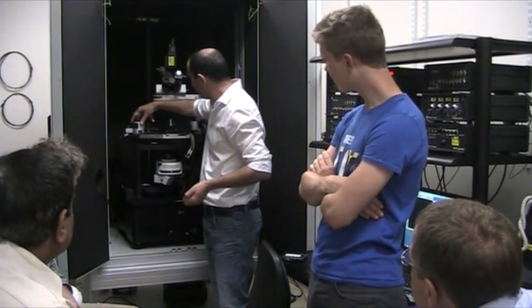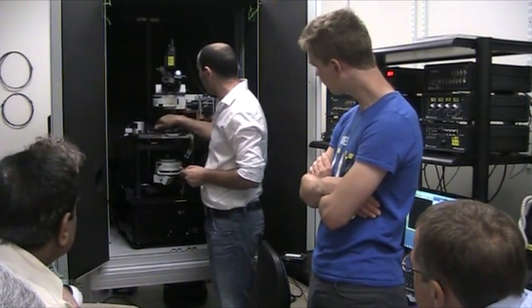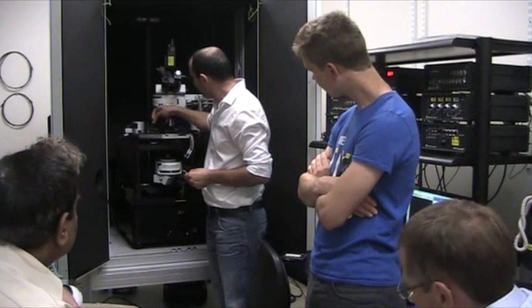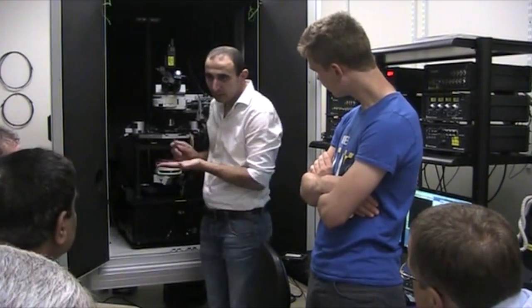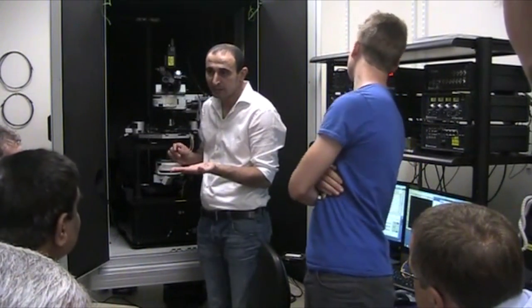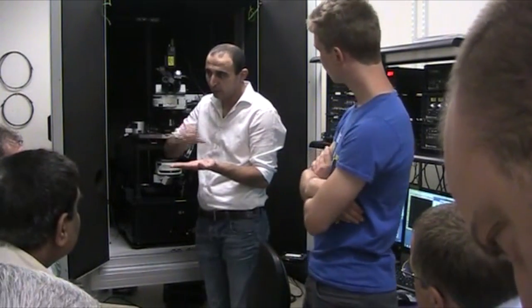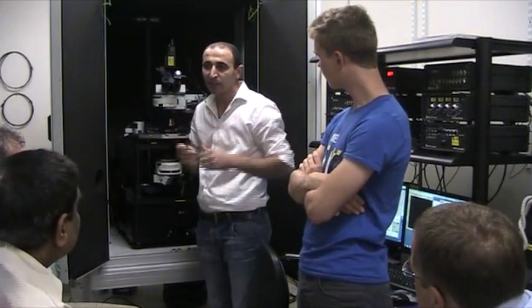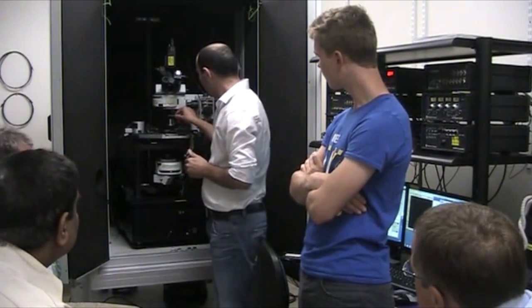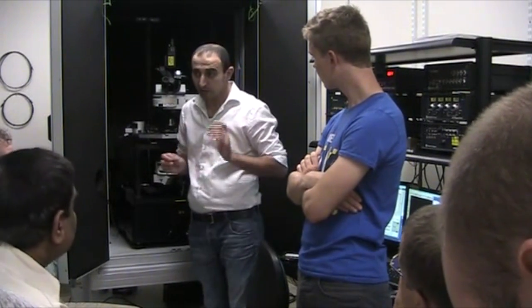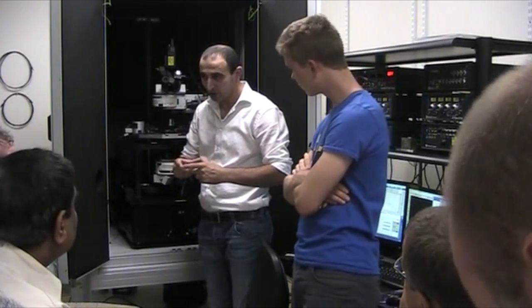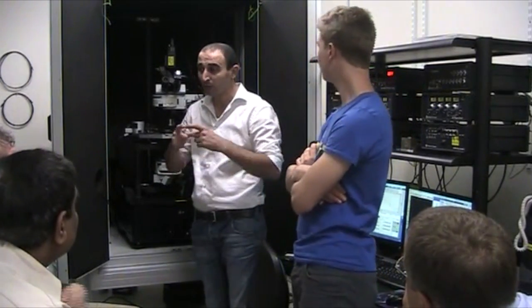this is the part. This is the AFM head together with the sample scanning stage. So in this system we have two AFM heads, okay? The right tower and the left tower. Every one of these towers also includes a tip scanning stage. So in general you have one sample stage, one to move the sample in X, Y, and Z, and an additional piezo for the first tip in X, Y, and Z, and the same for the second station. You could do up to 100 microns in X, Y, Z for the lower one. Notice also Z: due to the flat structure of the four piezo elements, you can do up to 200 microns.